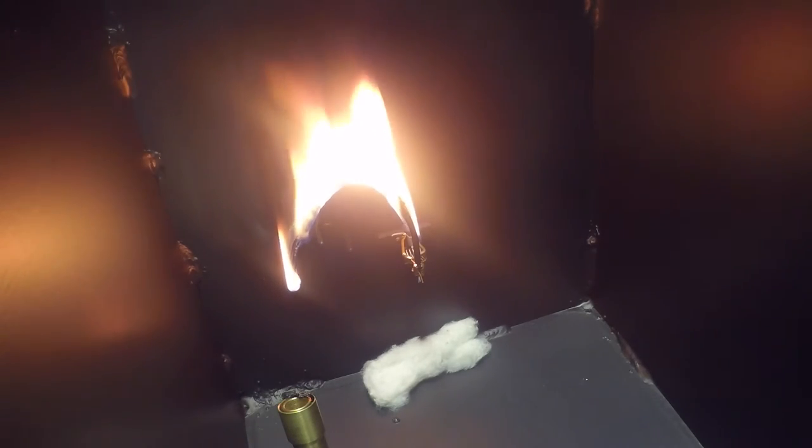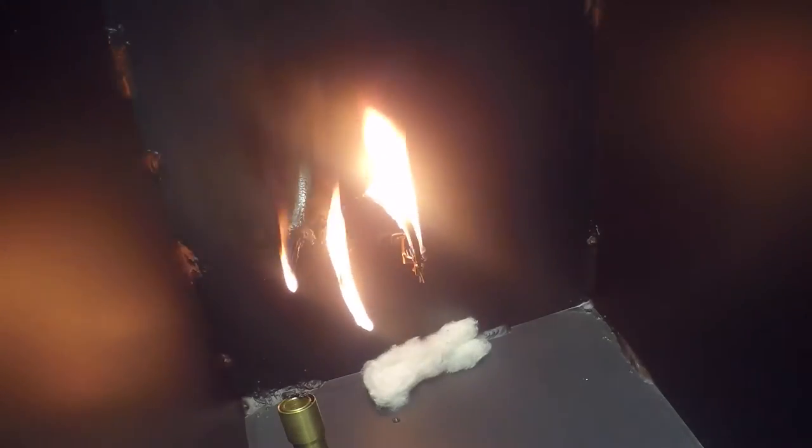This sample did not self-extinguish when the flame was removed, and the paper flag was 100% consumed. The drippings from the jacket and core ignited the surgical cotton at the bottom of the flame.